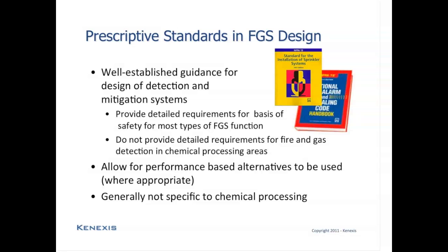But they do not provide the detailed requirements that are going to be required in chemical processing areas. Most of the fire alarm code and all of the other associated standards are really built around the protection of occupied buildings, such as office buildings, hospitals, schools. And they're not geared toward the very specialized requirements of processing flammable materials and processing toxic materials. Toxics are completely unaddressed by these codes.